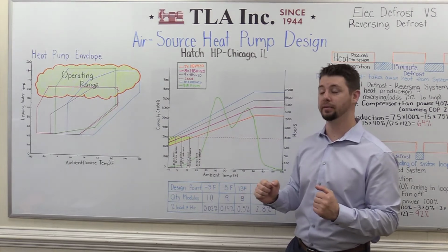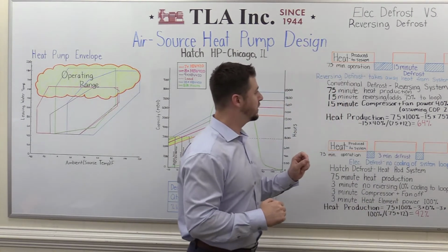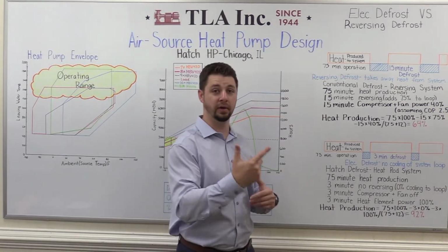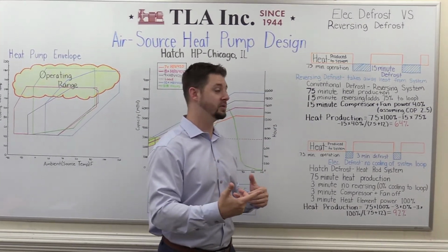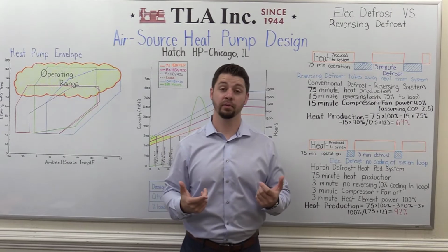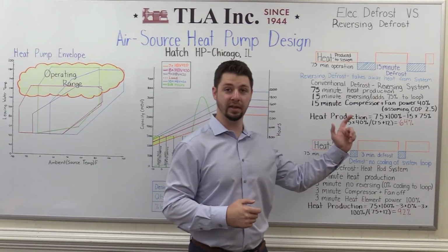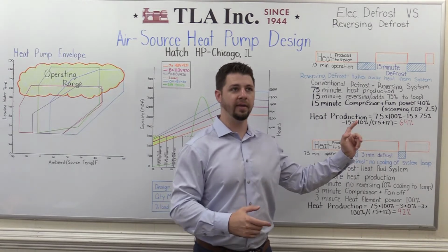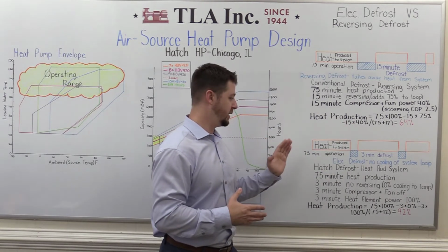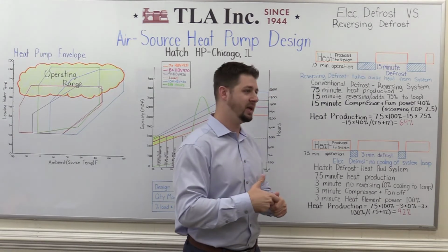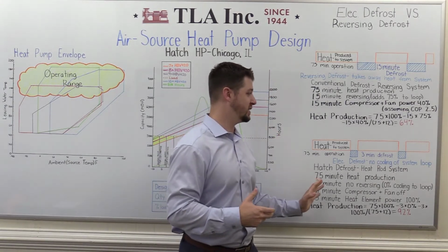straight electric heating. The last thing I want to keep in mind is that every heat pump goes through a defrost cycle on occasion, based on the demands put upon it. There's two different ways of approaching this. A lot of times you can reverse the heat pump, and an alternate way of doing it is straight resistive electric heat built within the coil circuit itself.